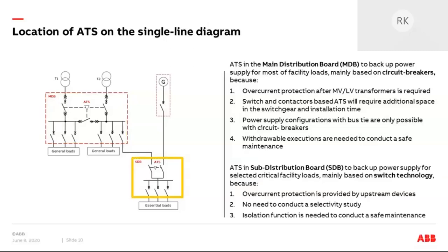ATS based on switch technology is usually located in sub-distribution boards to provide power continuity for selected critical loads. Switch-based solutions are preferable in this case because overcurrent protection can be provided by upstream devices. With circuit breaker-based ATS you would need to conduct a selectivity study, possibly over-size upstream circuit breakers, or use zone-selectivity. Finally, with switch-based ATSs you can simply padlock the unit in the zero or off position to conduct maintenance downstream of the ATS.